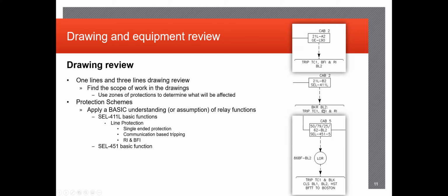So after we go through everything, the relay one lines are a big one, especially when you're upgrading relays out in the field. Identifying the protection schemes for each relay that you may be modifying. For instance, in this example, a 411L is a primary line protection relay for most clients. It's usually single-ended protection, communication-based tripping, offers reclose initiate or breaker failure initiate schemes as well. Whereas a SEL 451 is your primary breaker control protection. So breaker fail, reclosing, supervisory control, any alarms that may be associated with that specific breaker.